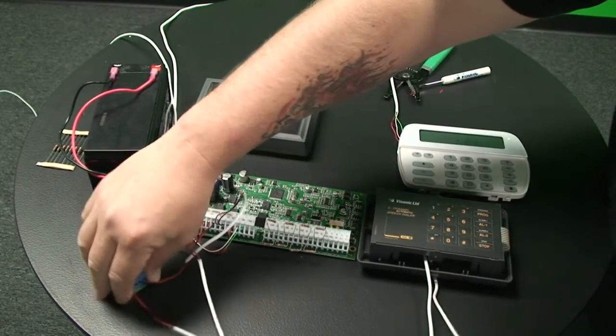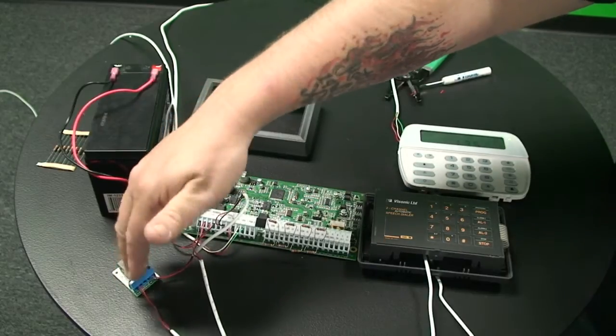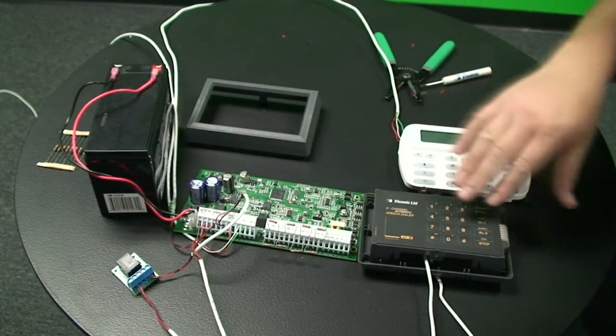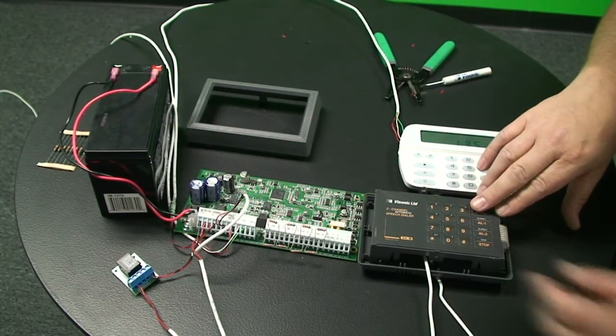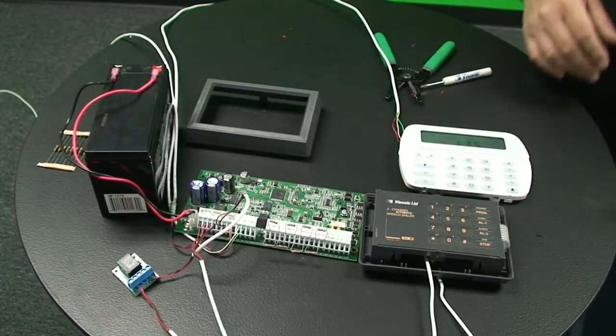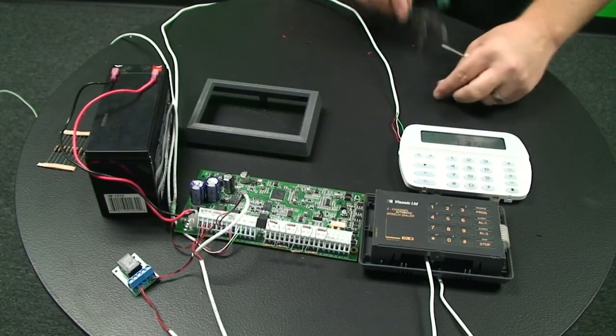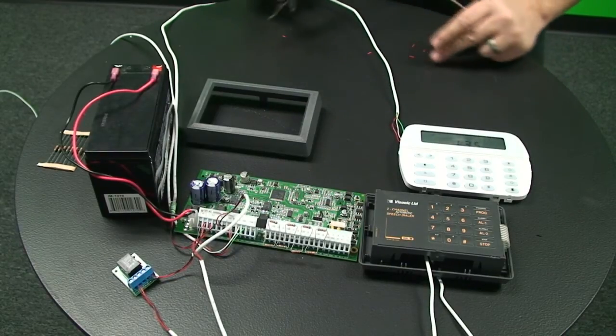And so what we have is we have our relay being fed from our control panel, and we have our normally open and common feeding our Z1 and negative on the dialer. And we've also supplied it power, and technically we've supplied it dial tone. So with that being said, that would be about it for the wiring on the dialer.